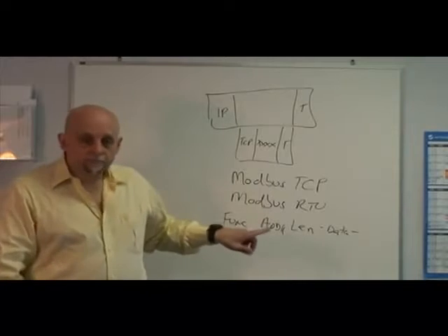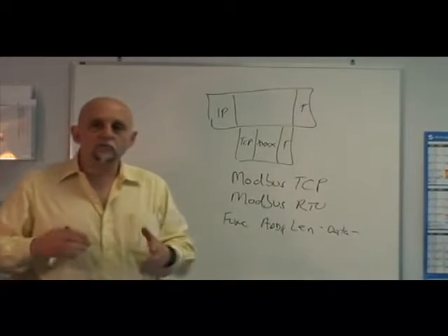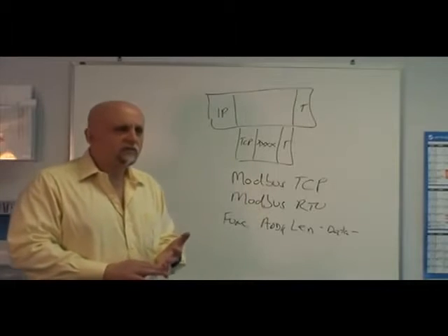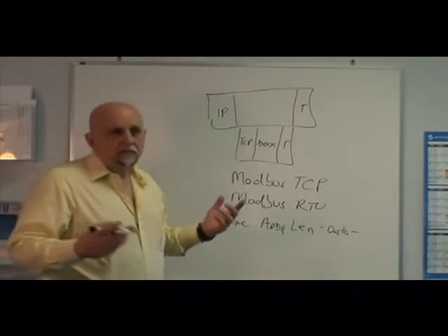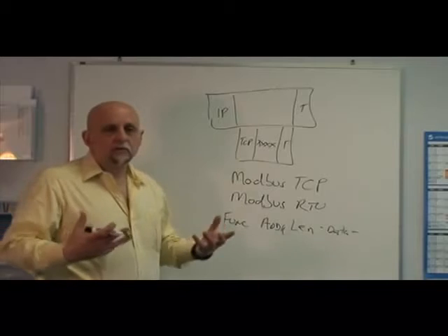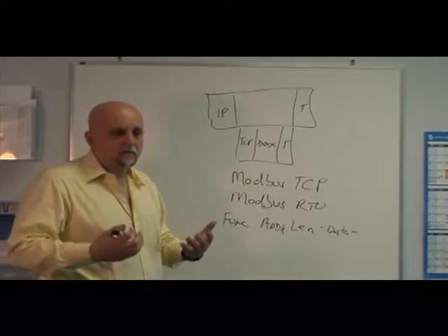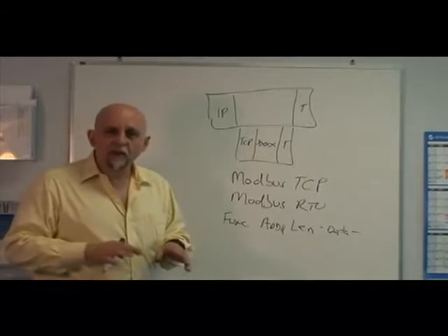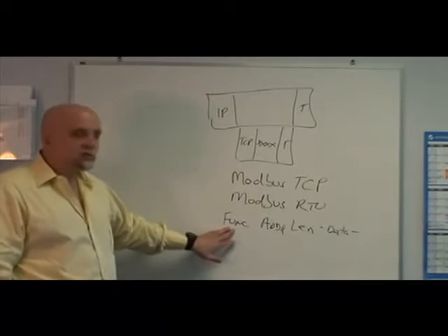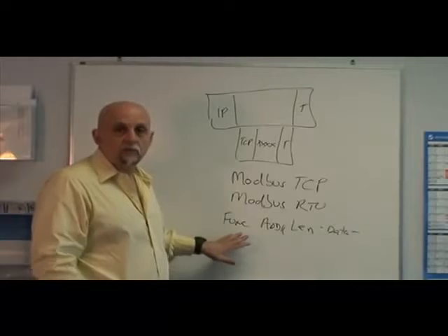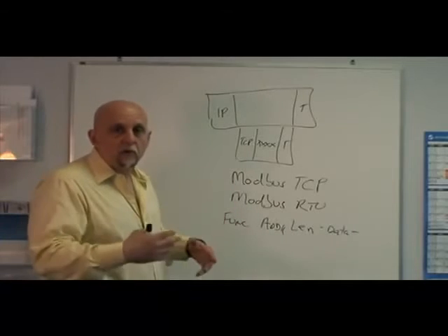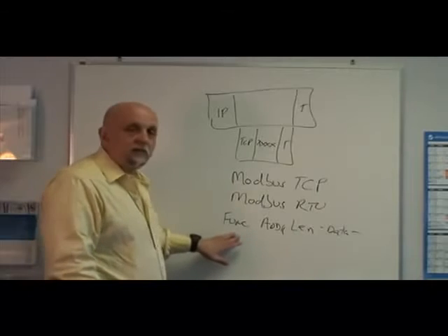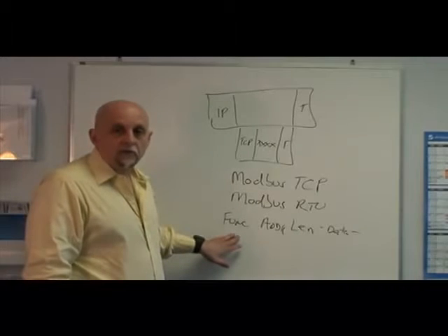So, function code. There are some function codes to read input registers, other function codes to read holding registers. In today's devices that are more virtual devices that have just a bank of memory that you're accessing, we've kind of gotten away from that. But some devices use function code 3, some devices use function code 4.